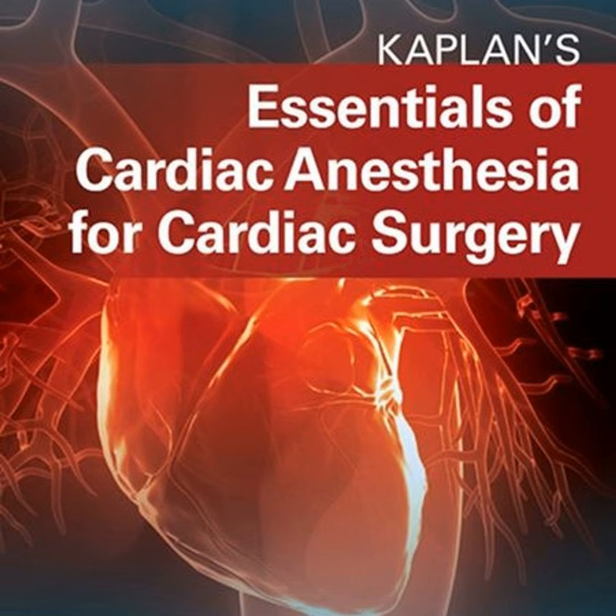The text dictates that surgeons must avoid monopolar ES entirely if possible, or tightly restrict their use to short, intermittent bursts of under 4 seconds. But the most fascinating protocol is the deployment of a specialized, heavy clinical magnet directly over the patient's chest. Right. Placing that magnet over the generator completely suspends the device's anti-tachycardia therapy. Yeah, it effectively blinds the ICD to the surgical interference, instructing the computer to ignore any chaotic high-rate signals and withhold all shock therapy. Crucially, though, the magnet does not disable the device's backup pacing function.